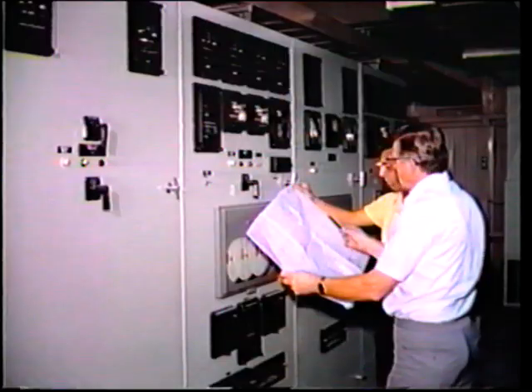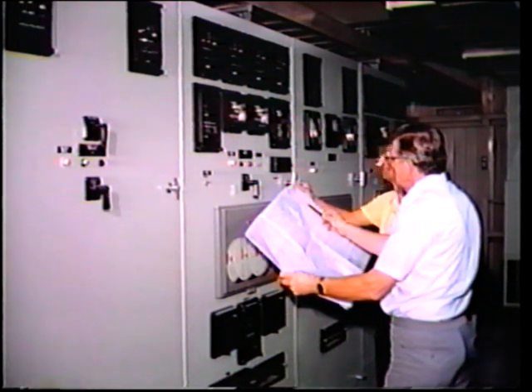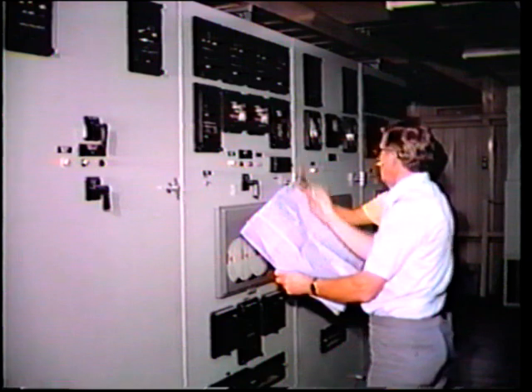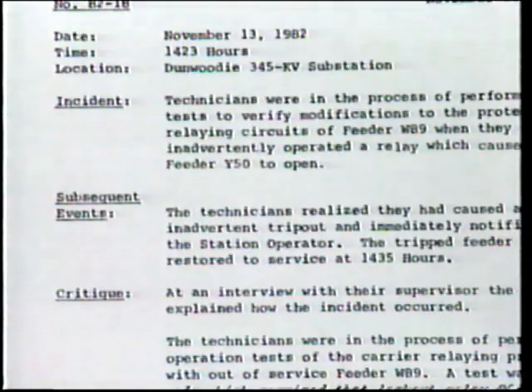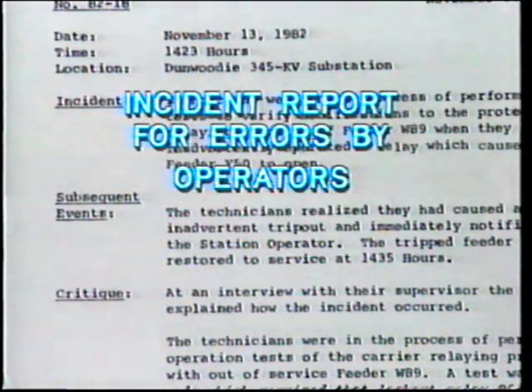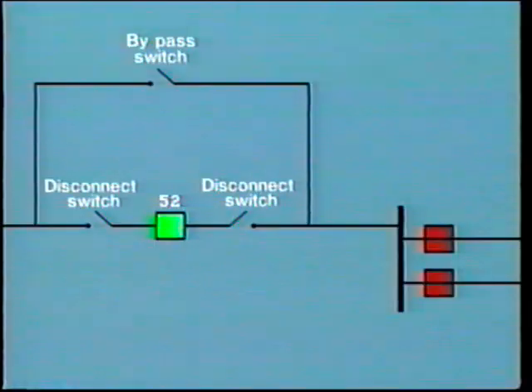The point here is that even though the circuit under test may be isolated, there is always the possibility of in-service equipment being disturbed. Now you can understand why the operators would rather not see relay technicians with their test equipment. It is most important that all of these incidents of inadvertent tripping be reported and thoroughly investigated. Don't try to cover up. A written incident report should then be circulated so that all interested parties can learn from the experience. In most companies, incident reports are also prepared for misoperation due to operator error or other maintenance technicians, electricians, and mechanics. Here is another incident.